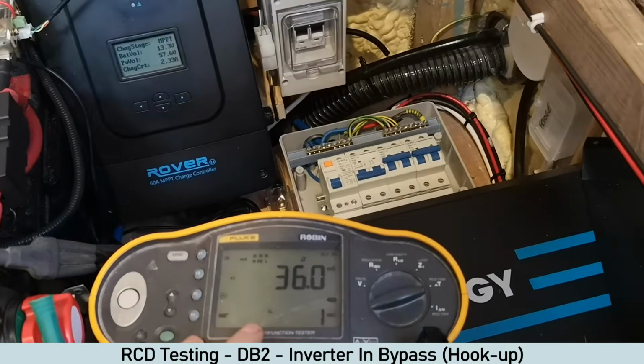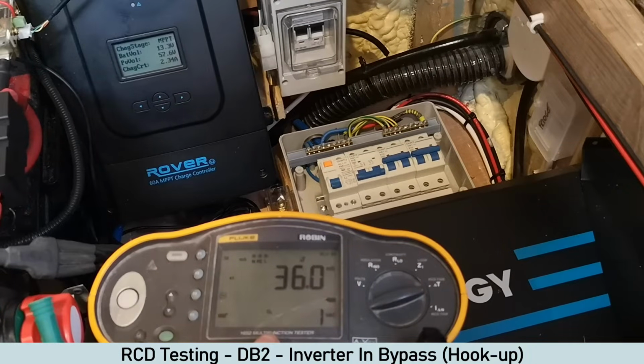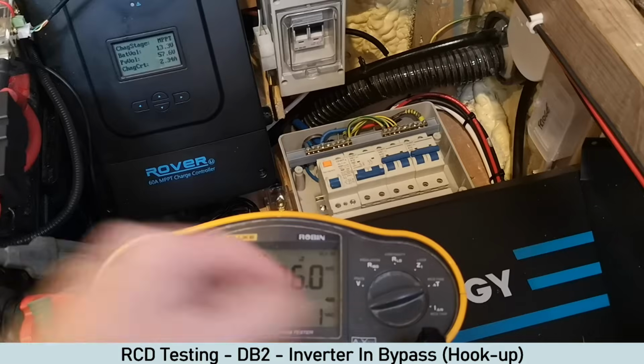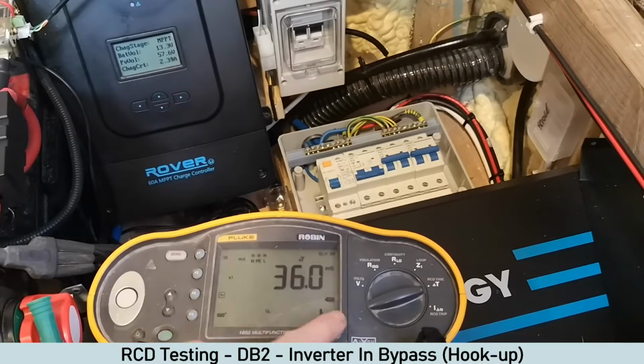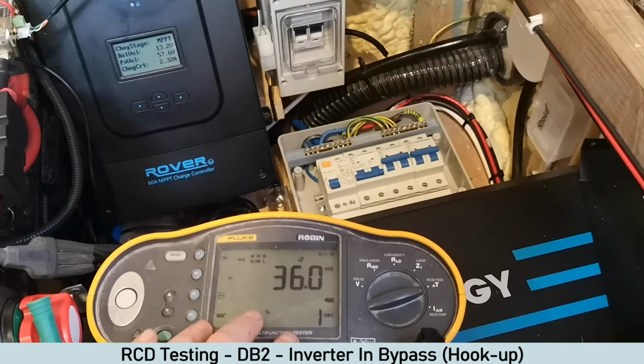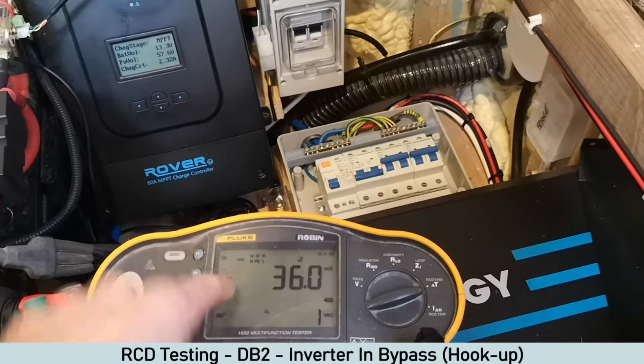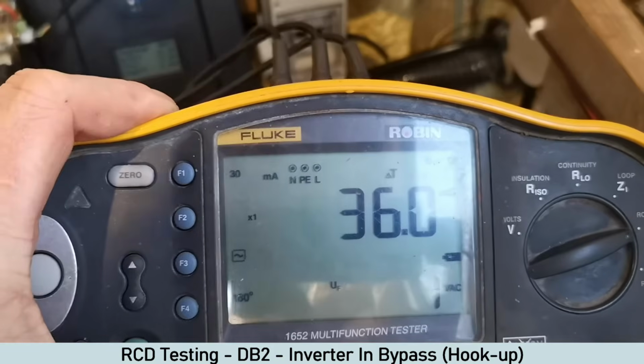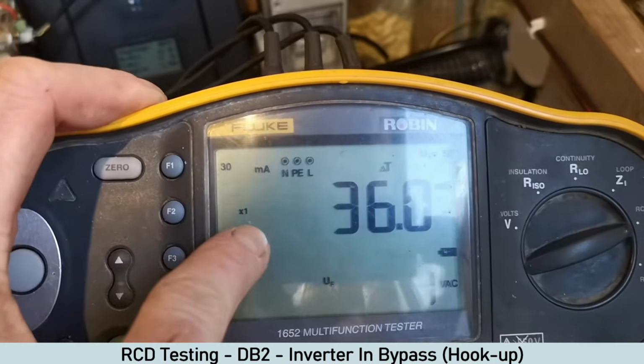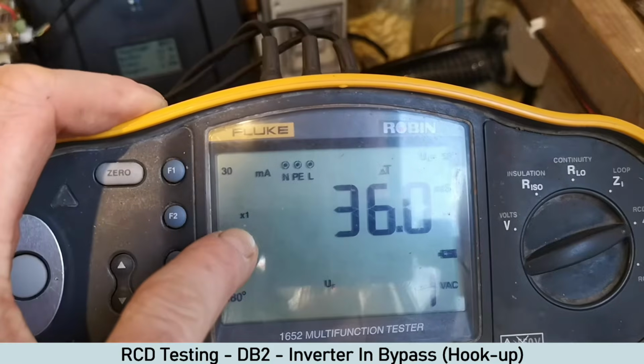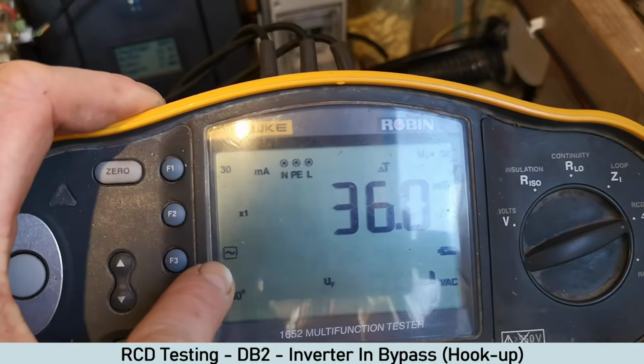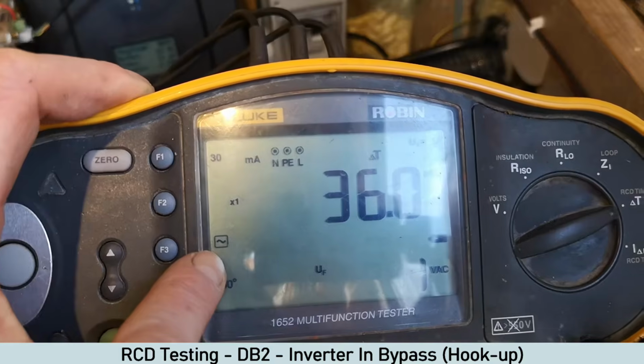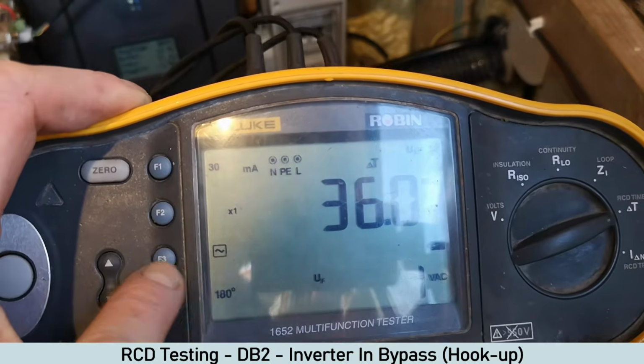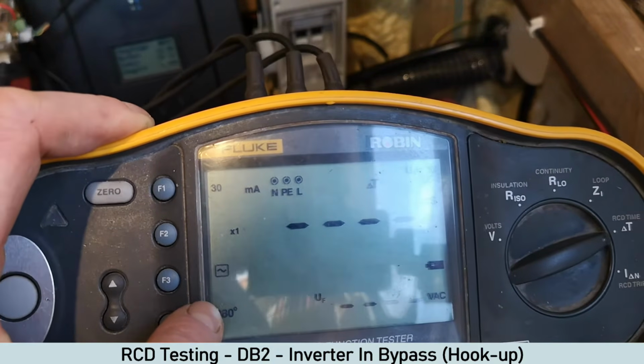So this is my tester. It's a Fluke multifunction tester with an RCD test function. You see the RCD test, specifically to test RCDs. So I've got it set to, let me zoom in a bit, 30 milliamps to test a 30 milliamp RCD. 1 times, which means I'm testing at 30 milliamps. And it's set to AC, because the regulations now just say whatever RCD you're testing, test it at AC. And the regs also say now that it needs to trip in less than 300 milliseconds to pass.